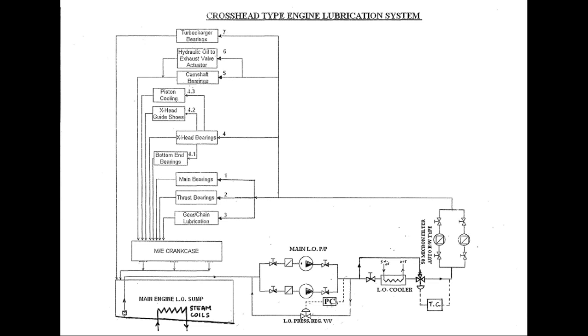Lube oil pumps for two-stroke crosshead engines are not engine-driven but are electric motor driven, as shown here with the pumps and their motors. They are provided in redundancy — pumps are provided in duplicate and work in auto standby mode. Failure of one pump or loss in lube oil pressure will automatically start the standby pump if auto standby mode is selected.